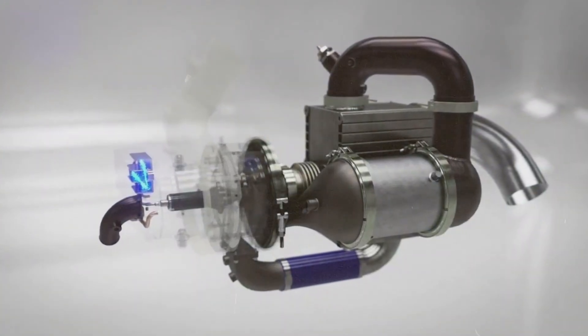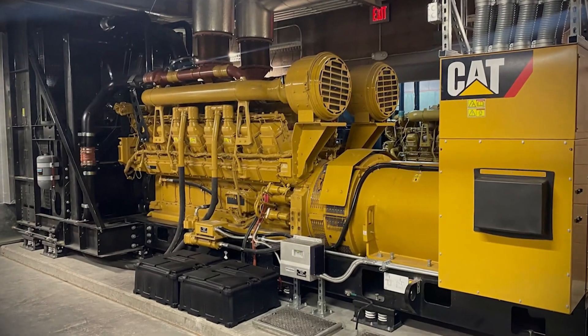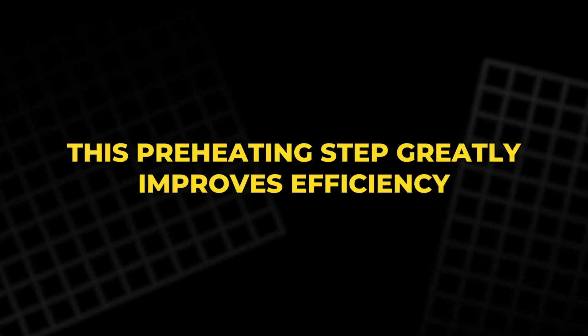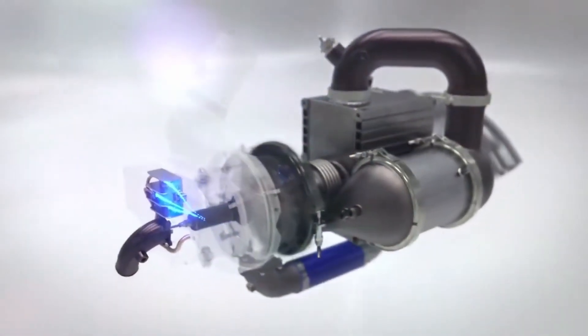As the compressed air flows through the recuperator, it passes over surfaces heated by the outgoing exhaust gases. This raises the incoming air temperature before fuel is introduced. This preheating step greatly improves efficiency because it means the fuel must supply only part of the energy needed to reach the final reaction temperature.